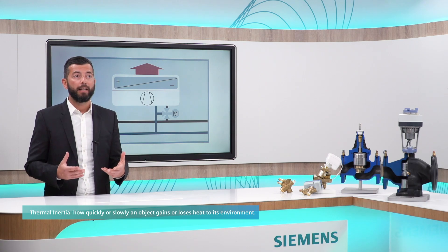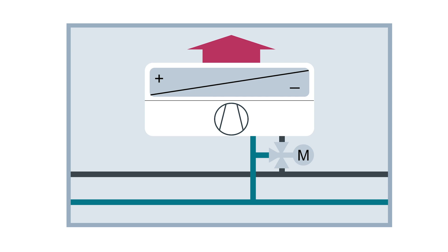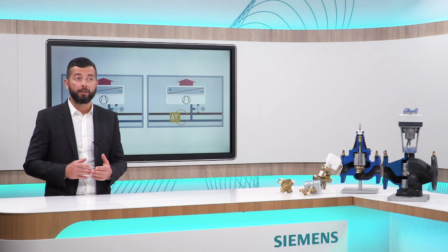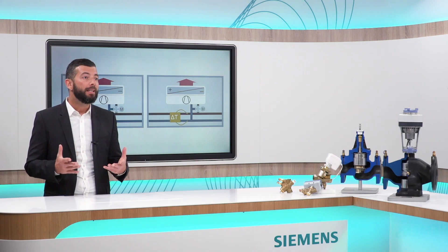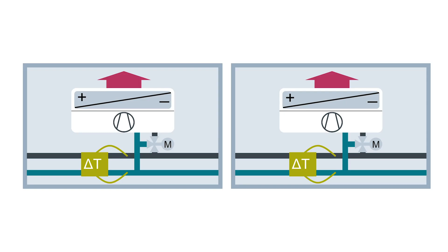A low inertia is the capability to quickly transfer the energy from the water into the air, so that the system can be operated with a fairly high temperature difference between flow and return pipes at the heat exchanger. This means that you switch from a constant volume system design with three-port valves to a dynamically variable flow system with speed-controlled pumps and two-port valves.